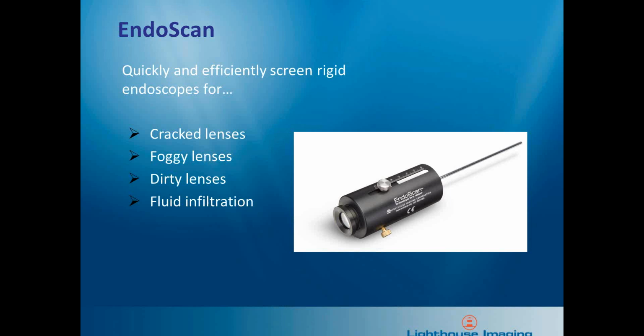So again, we'll start with the simplest, and we'll talk a little bit about the EndoScan. The EndoScan allows you to quickly and efficiently screen rigid endoscopes for internal damage, such as cracked lenses, foggy lenses, dirty lenses, which typically comes from two sources. Dirt on lenses can come from either a poor environment during assembly in a third-party repair, for instance, or it can also come from degradation inside the components if they're starting to break down and create some debris inside during operation. And then also fluid infiltration can be detected.